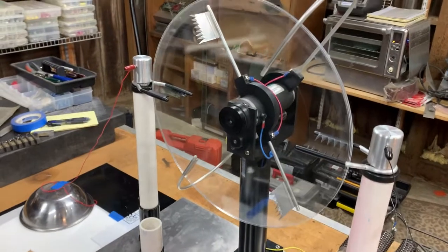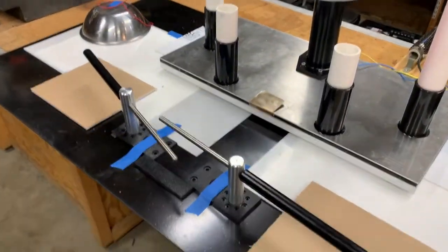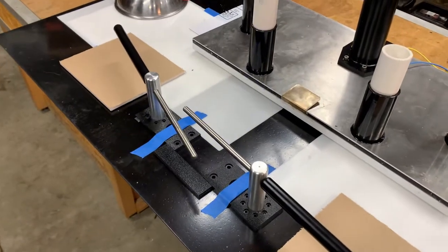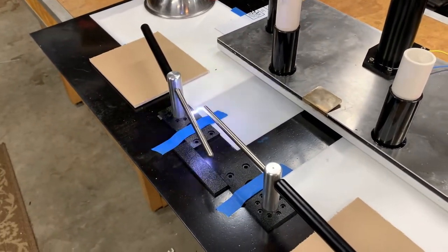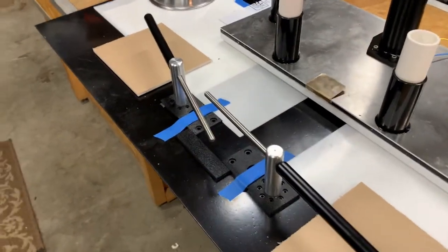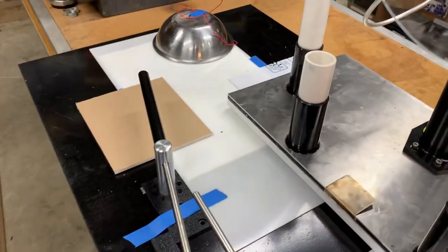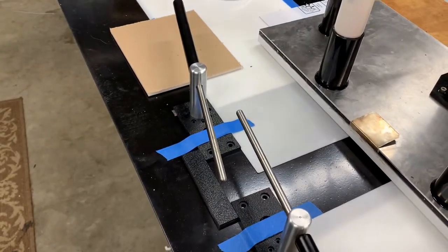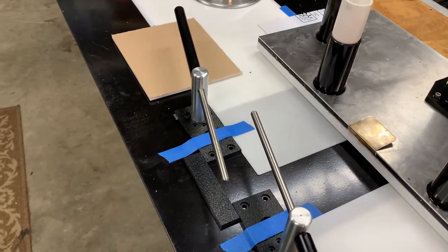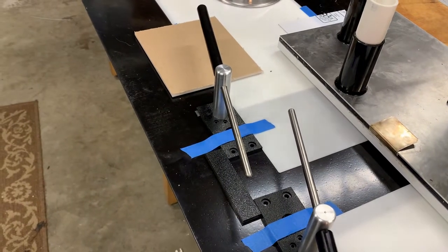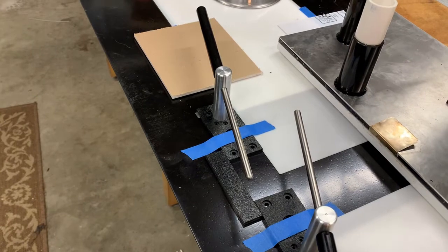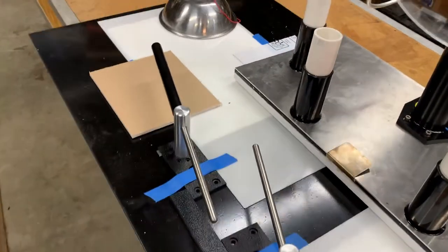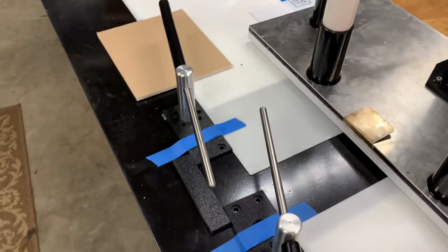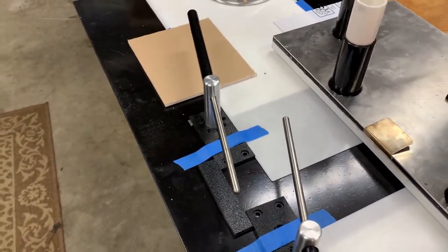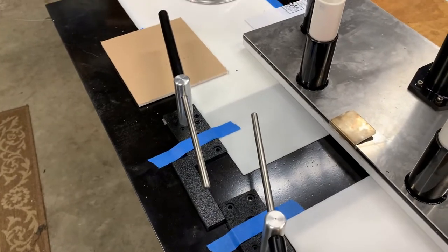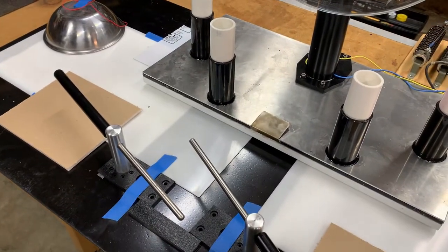So the machine's now running. You can hear it's pretty noisy. You won't be able to see all the sparks from the phone because the shutter speed won't always be synchronized with it. But we've got a fairly short spark gap there. So I can start increasing it. So that's about the practical limit. I'll stop the machine now and we'll measure that gap. Well, that gap turns out to be about 90 millimeters.